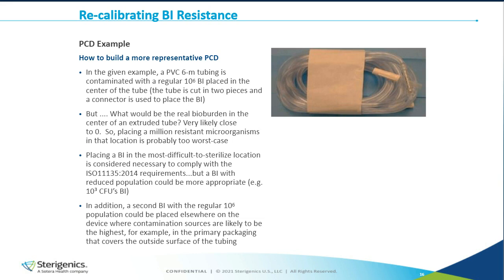Maybe this is not the best that we can do to optimize the PCD selection. So in order to still be compliant with the 11135 standards, we can still use a BI in that location, but maybe place a 10 to the 3 BI that will cover a potential bioburden, and place a 10 to the 6 BI in the primary packaging where the tubing bioburden would reside. So it means that the bioburden is likely to be more present on the outer surface of that tubing when it's rolled and placed in the primary packaging rather than inside this tubing.